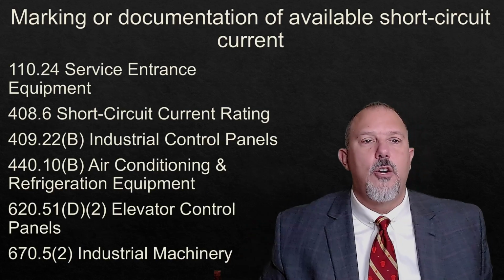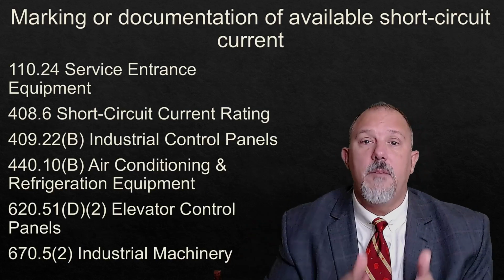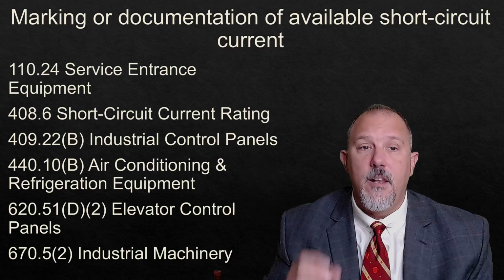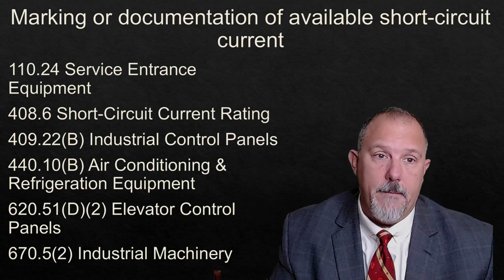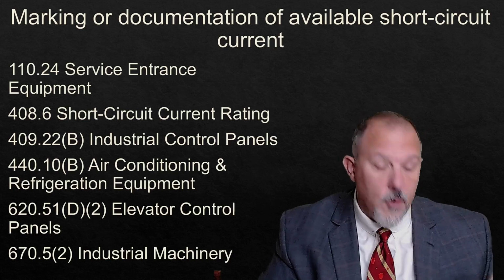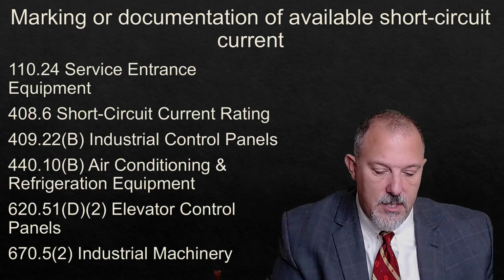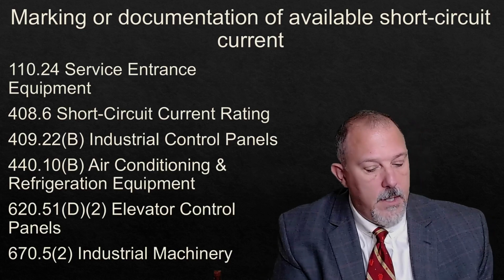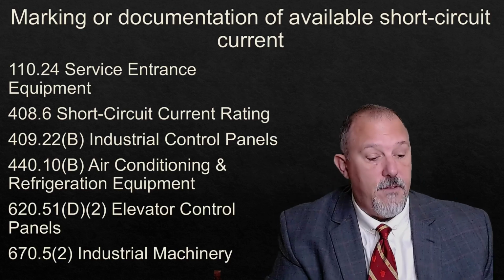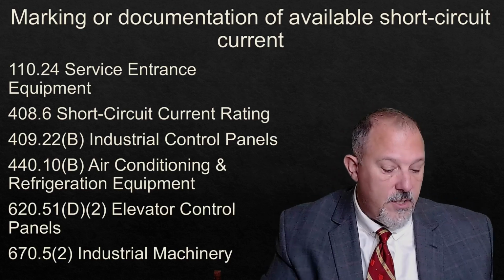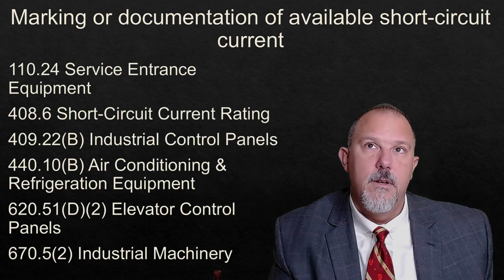These are the sections of the code where you have either a marking or a documentation requirement of available short circuit current of that equipment. So like in 110.24, and we read it earlier, what does 110.24 tell us? I'm going to read it again for you. 110.24.